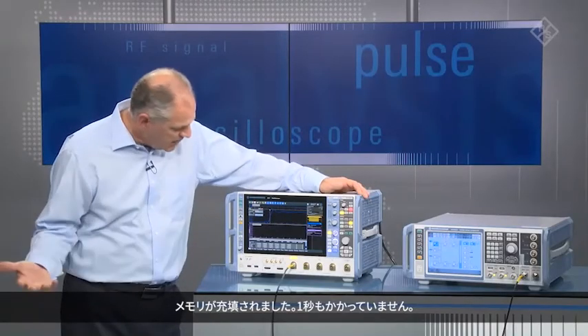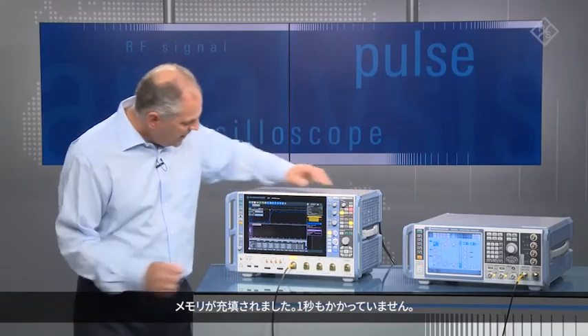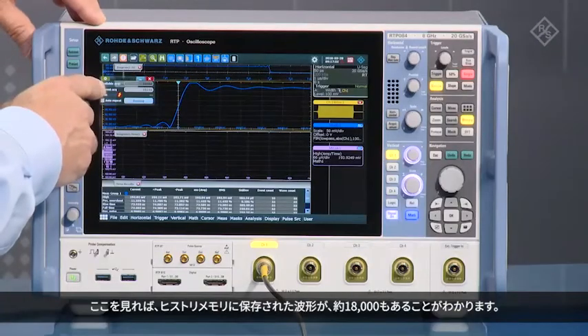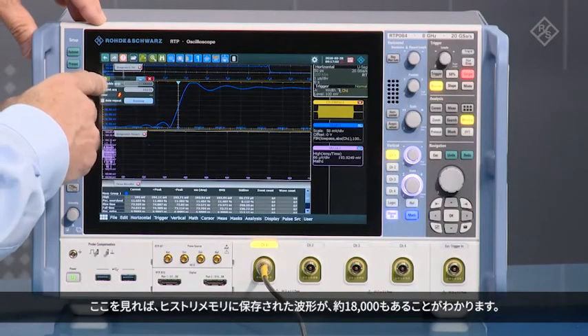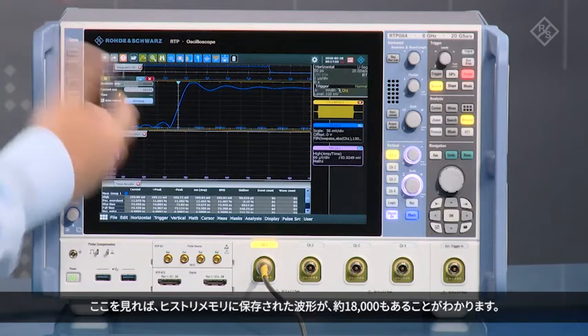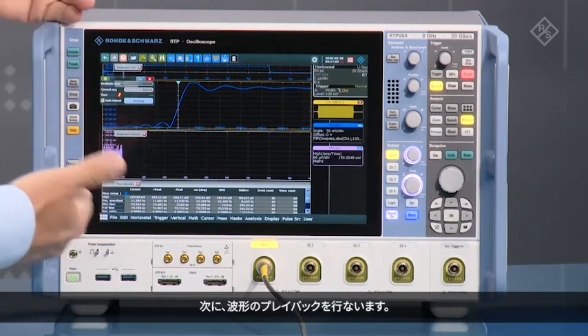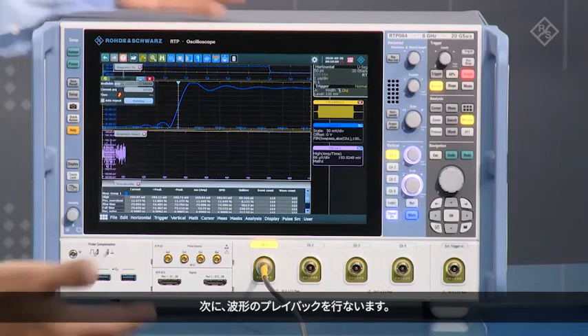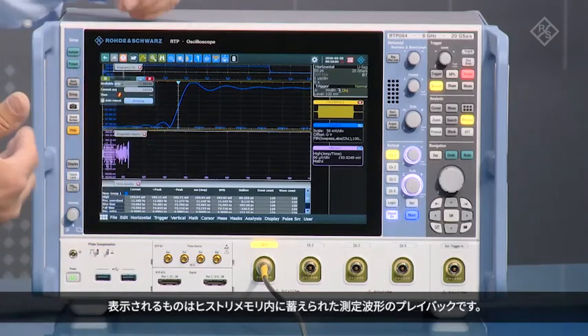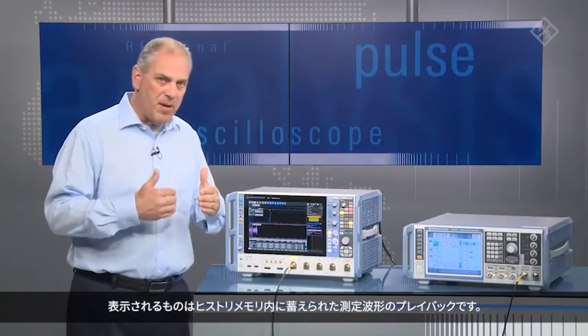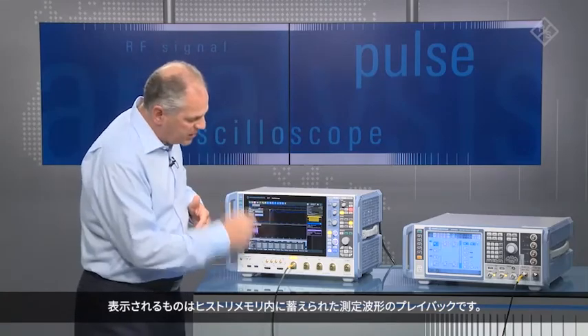So now it's done filling the memory. It took, I guess, seems like less than a second. And if we look in here, we can see on the top here that there is a history that's stored. And we have about 18,000 waveforms, and right now the instrument is sort of playing those waveforms back. So what you see on the screen here is that history of waveforms in memory being played back and the measurements being tracked on the screen.